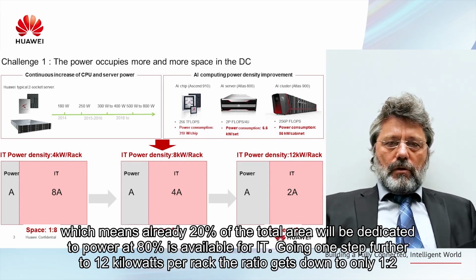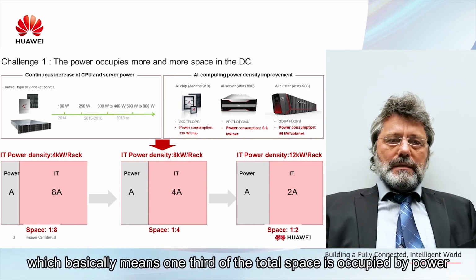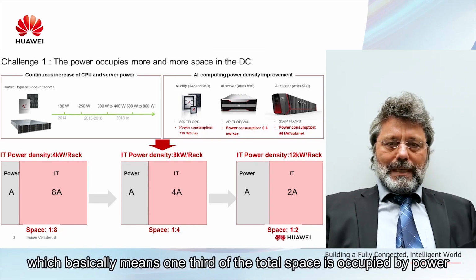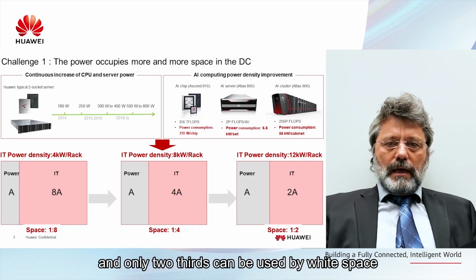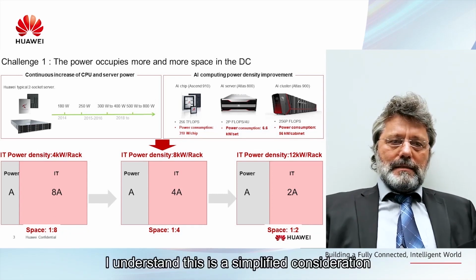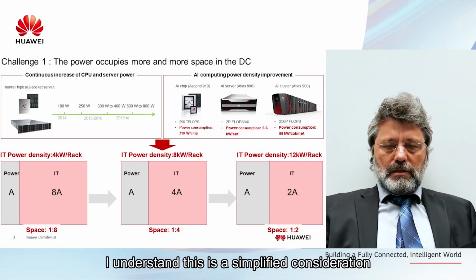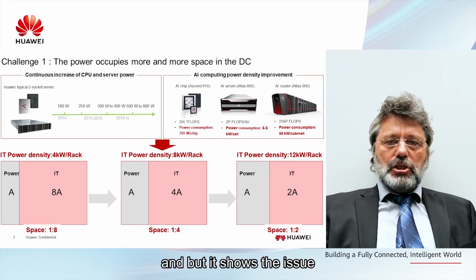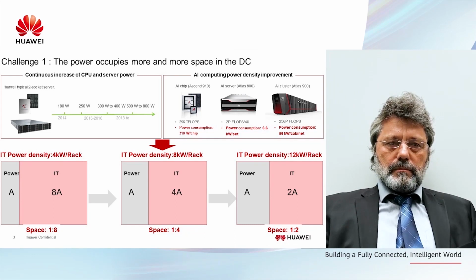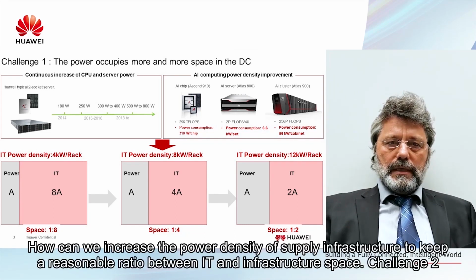Going one step further to 12 kilowatts per rack, the ratio gets down to only 1:2, which basically means 1/3 of the total space is occupied by power and only 2/3 can be used by white space. I understand this is a simplified consideration, but it shows the issue. How can we increase the power density of the supply infrastructure to keep a reasonable ratio between IT and infrastructure space?